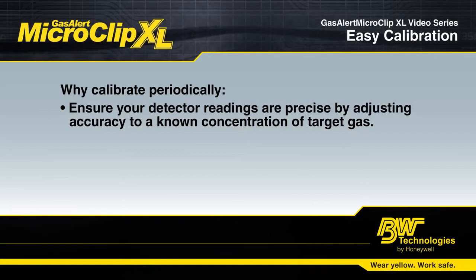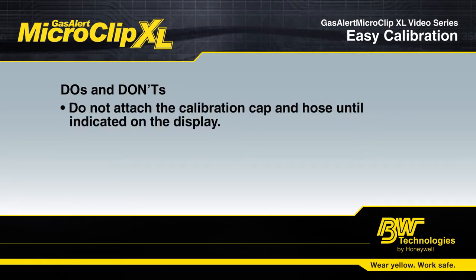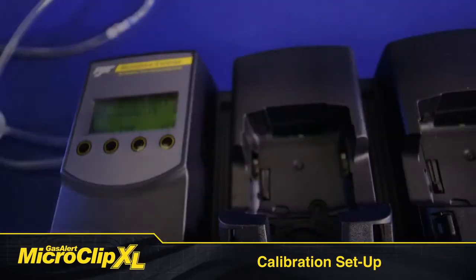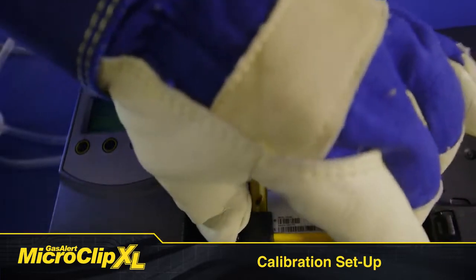Before you start calibration, make sure that you are using good quality gas from a reputable supplier. During manual calibration, do not attach the calibration cap and hose until indicated on the display. For automatic calibration with the docking station, make sure your system is properly assembled. When initiating calibration, make sure you are in a fresh air environment. There shouldn't be any contaminating background gas and you should be in an atmosphere of 20.9% oxygen.